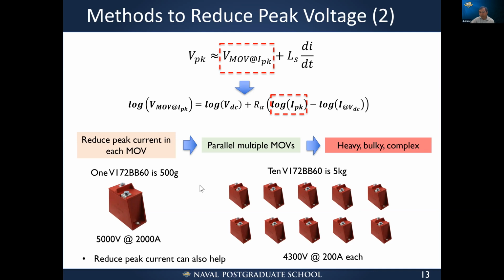This MOV is 500 grams, 10 of them is 5 kilograms, and I only have 12 kilograms of budget per pole, right? And also, how can you connect so many MOVs in parallel? Probably you have to use a laminated bus bar to do this, because you also have to guarantee good current sharing among the devices, right? It will make it complicated and bring insulation design challenges. And of course, if you can reduce the peak current directly, that'd be great.